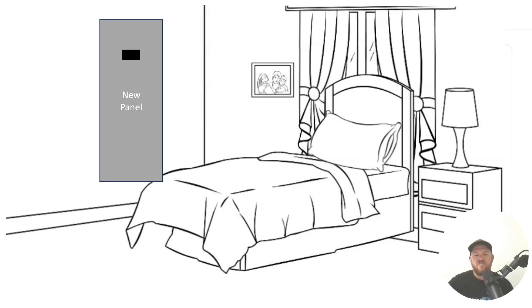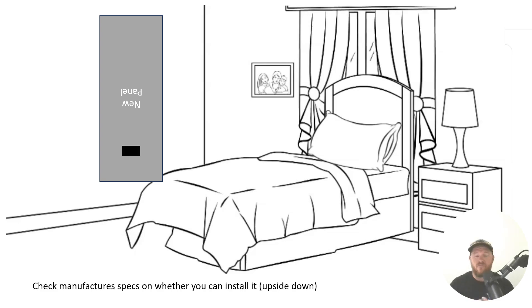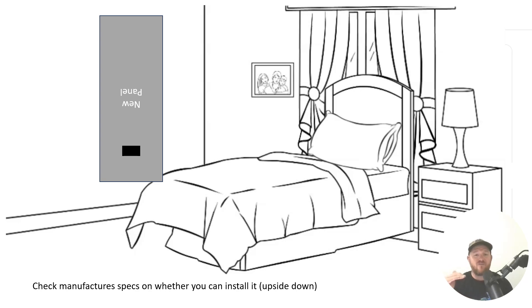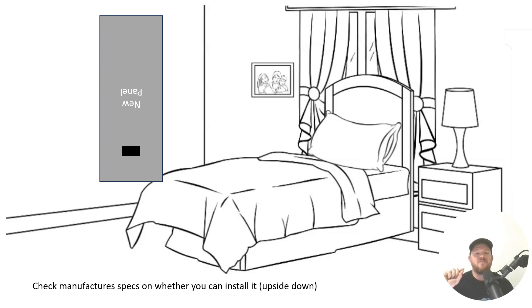So you decide that you're going to flip this panel upside down and put your main breaker on the bottom. Not a problem. As long as the breaker goes from left to right, then you're okay. It cannot ever be installed that if it's an up and down breaker that it's in the off position while it's up.